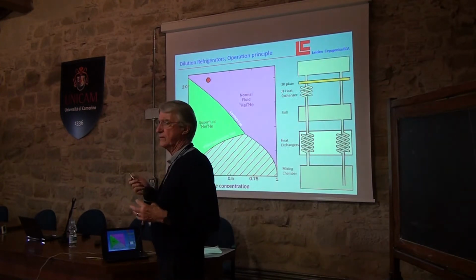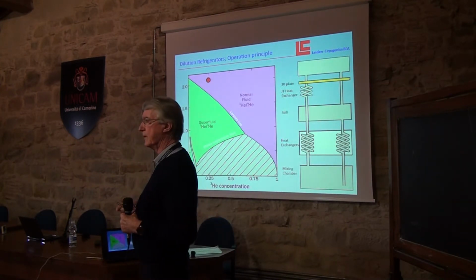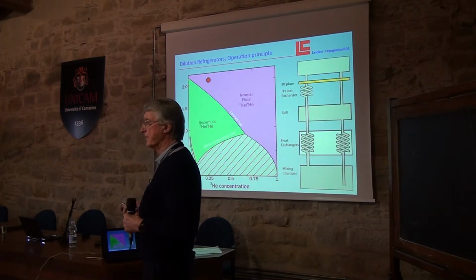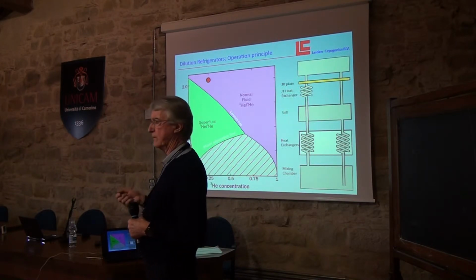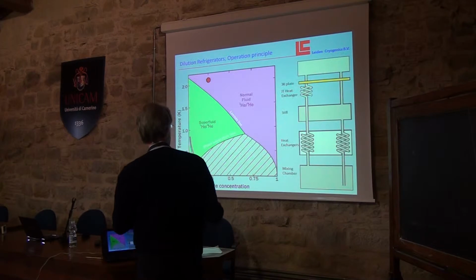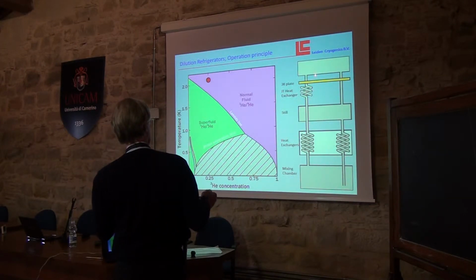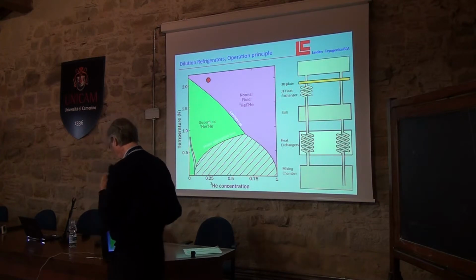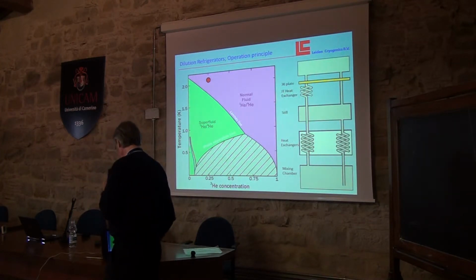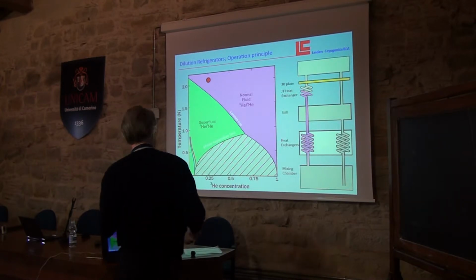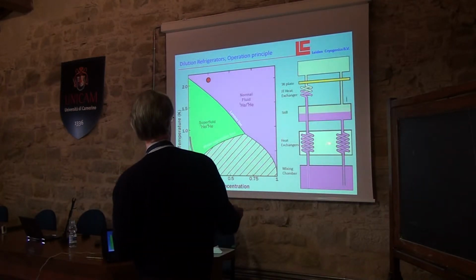Nowadays, since 6 or 7 years, we have substituted liquid helium by a commercial pulse-tube refrigerator, which makes things much, much cheaper in the long run, since helium is very expensive. And so this 3 Kelvin plate is cold now, so that your mixture of gas, in this case with 35% helium-3, can condense and then can fill up the whole machine up to a given level here in the still, which is where it evaporates. So that's what happens. The mixture fills up the refrigerator.